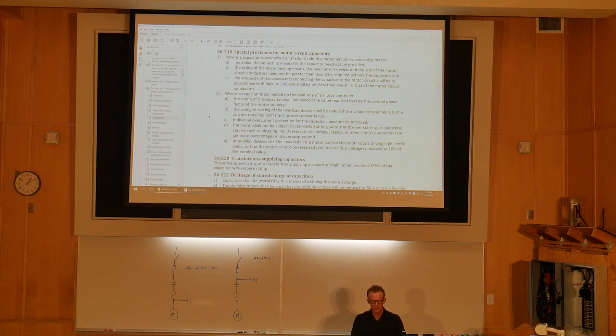B, the rating or setting of the overload device shall be reduced to a value corresponding to the current obtained with the improved power factor. So now this capacitor is going to reduce the current through the overload here. We must reduce the size of the overload setting. Here, the capacitor still gets to see the full motor current. C, individual overcurrent protection for the capacitor need not be provided, because we're going to use this fuse here on the motor. It's going to do overcurrent protection for the capacitor and the motor at the same time.